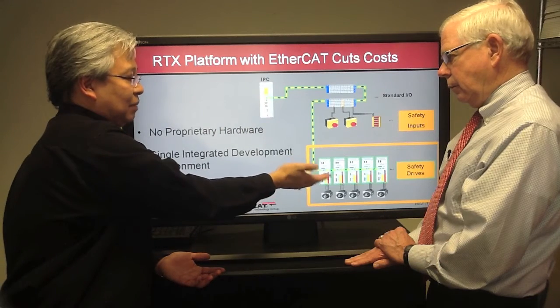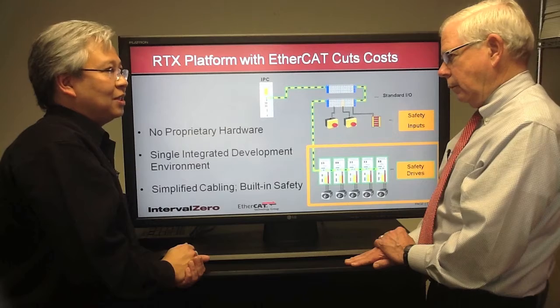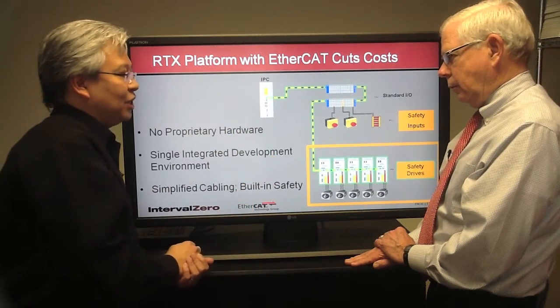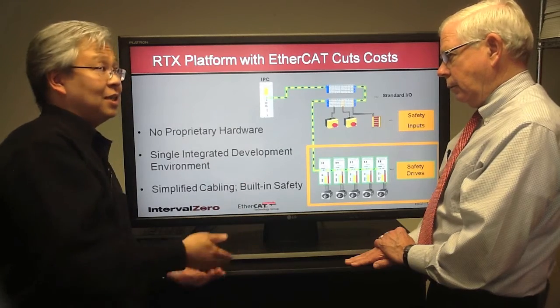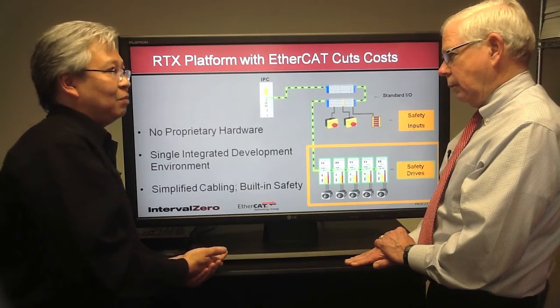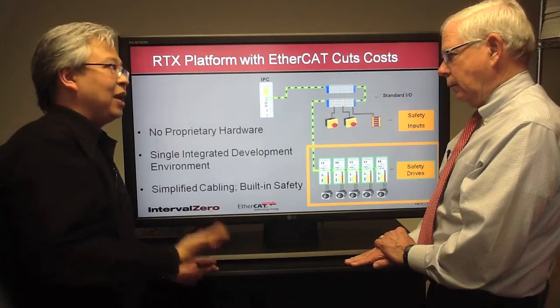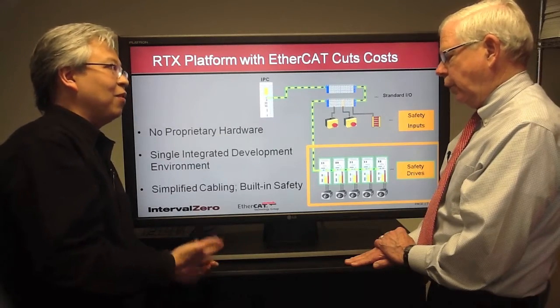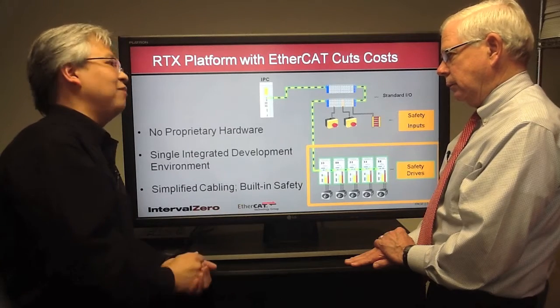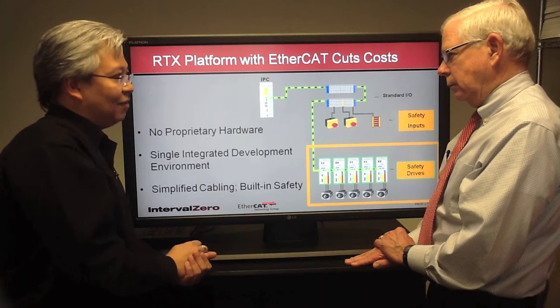EtherCAT can reach a safety integrity level of SIL 3, which is the second highest. Also worth mentioning: if you're moving from an existing bus technology, EtherCAT protects your investment because you can buy plug-in modules that support CAN Open, DeviceNet, and Profinet — all plugging onto the same e-bus or EtherCAT bus. So you can truly leverage your existing hardware and software investment today while still taking advantage of EtherCAT.